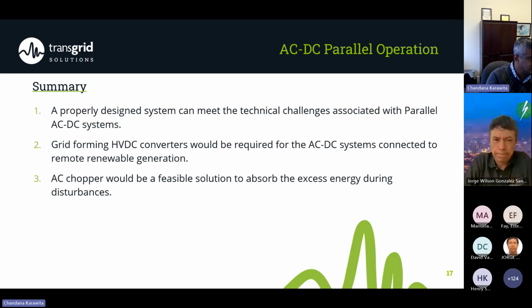When you do the switching studies, you have to consider the faults in both of the systems and design for the two systems together. It's very important. So even if you are going to have both AC and DC on the same tower, it would be quite challenging, and you may have to change the arresters connected to the AC system as well. So these things should be carefully evaluated at the design stage. Yes.